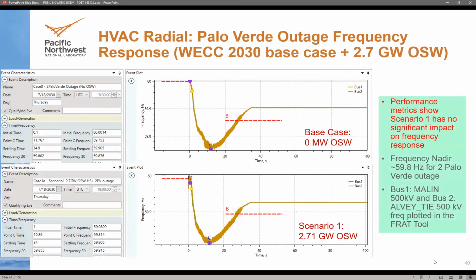So this is our HVAC radial case, with the two Palo Verde outage. You see some oscillations there, primarily because some of the models need further tuning, and we did use a full WECC case for this particular analysis. What we observed was a frequency nadir of 59.8 hertz following the two Palo Verde outage, which is very much within the benchmark results and performance requirements for the WECC system.